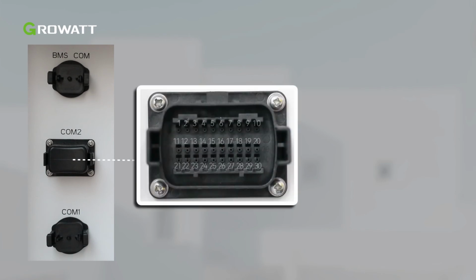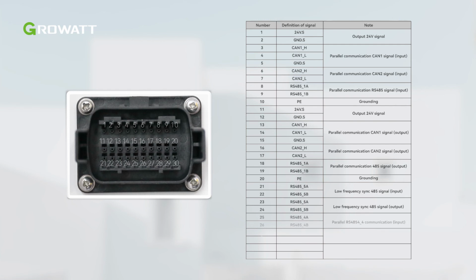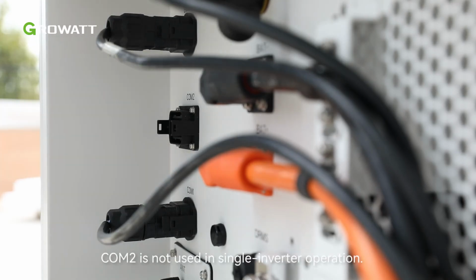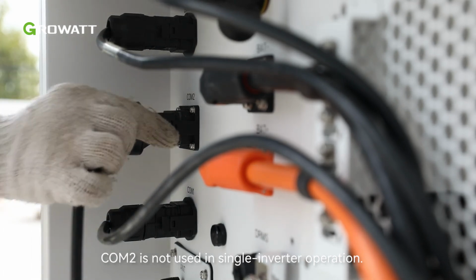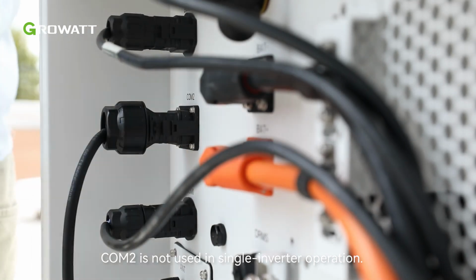The parallel communication terminal COM2 of the WIT inverter uses a 30-pin terminal. Connect the communication cables to the corresponding terminals as required. Remove the dust-proof cover from the COM2 terminal and insert the 30-pin terminal, the client side, to the corresponding position.